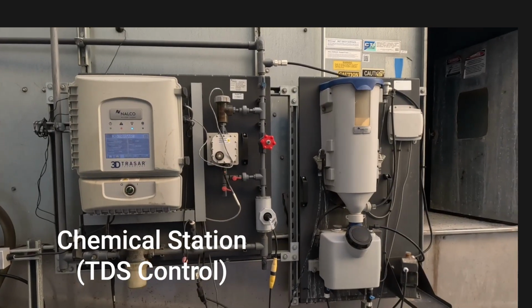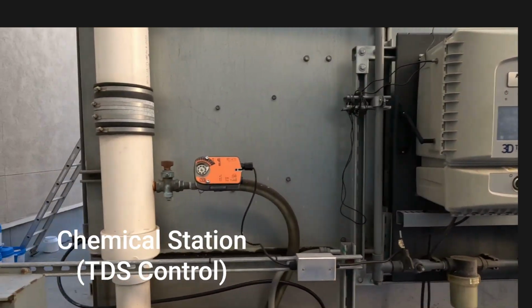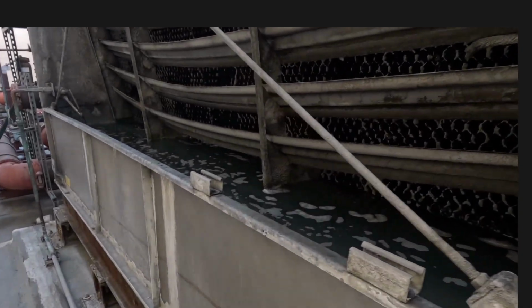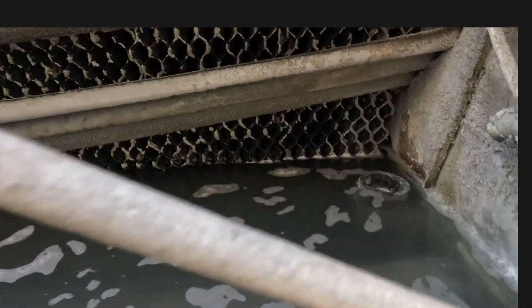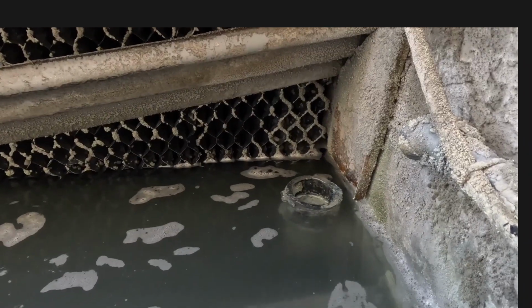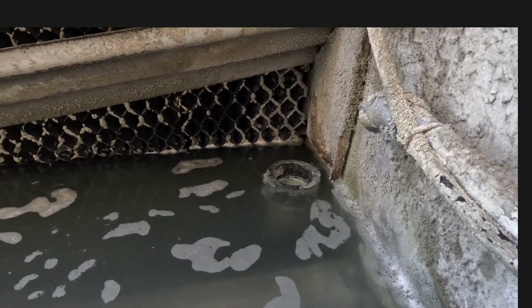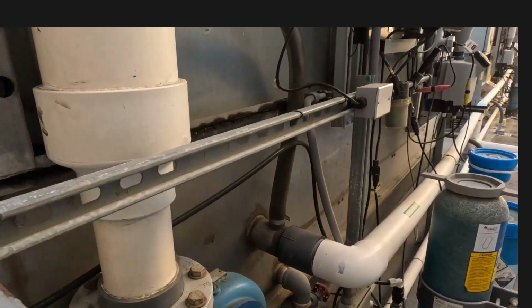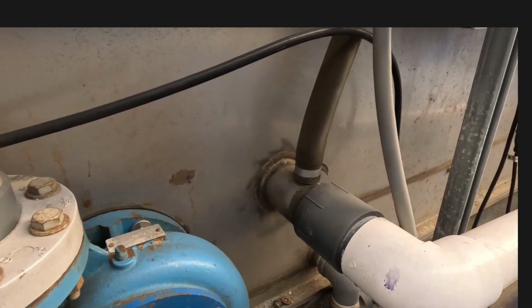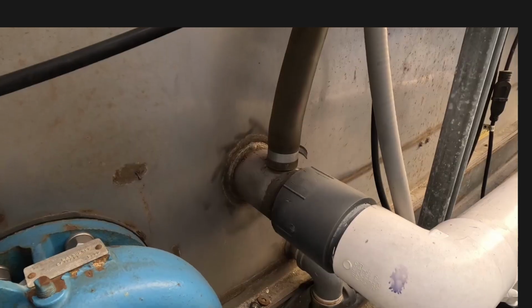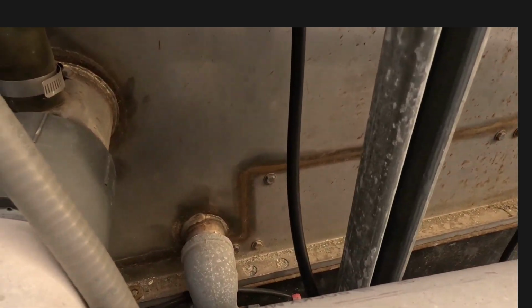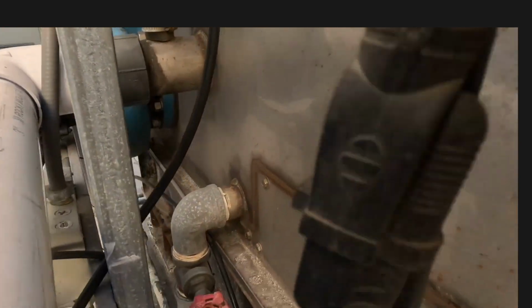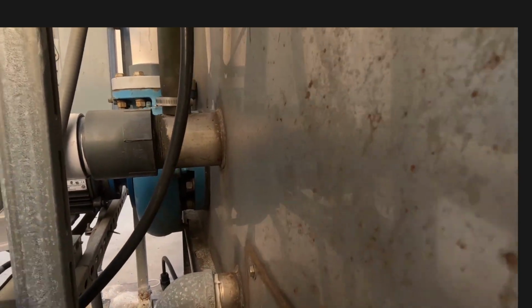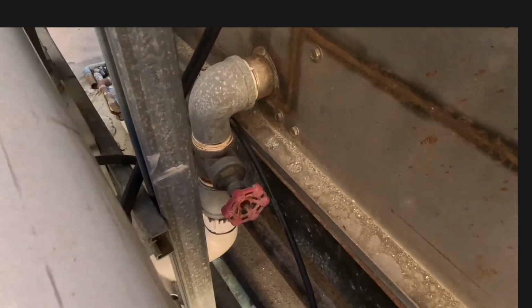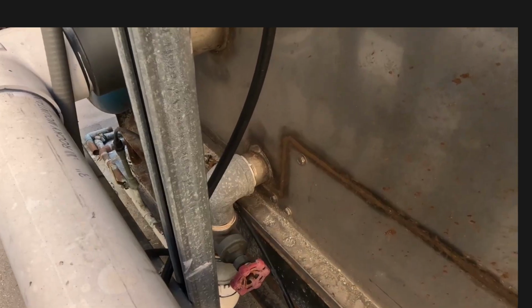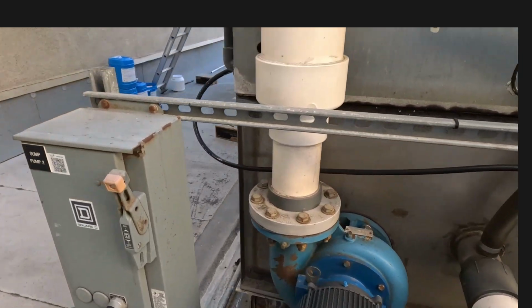Your chemical station, chemical to prevent the total dissolved solids, the TDSs, in your condenser water here. And you can see in this tower, it's overflowing a bit. And that's what that is. That's the overflow. So you actually have two drains on these cooling towers. You have an overflow drain, which is that one. And then you have your main drain, which is that one. You can see the overflow drain is higher than your main drain. So you want to open the main drain when you're cleaning these cooling towers so you can drain all the water that's inside of them.